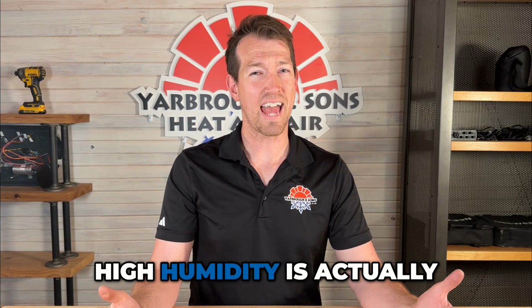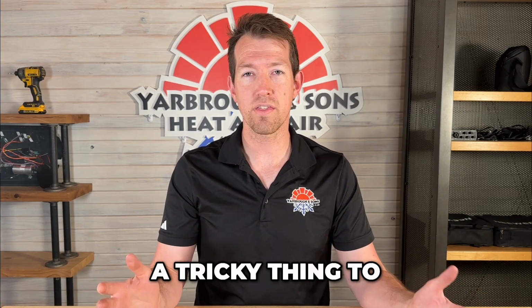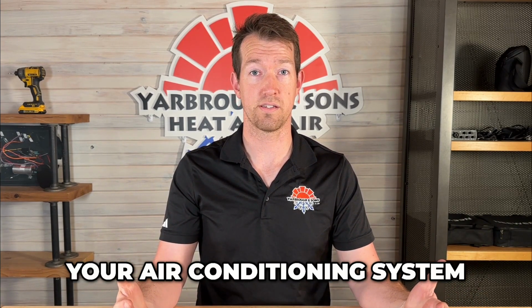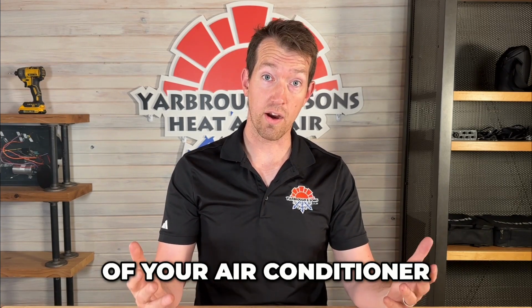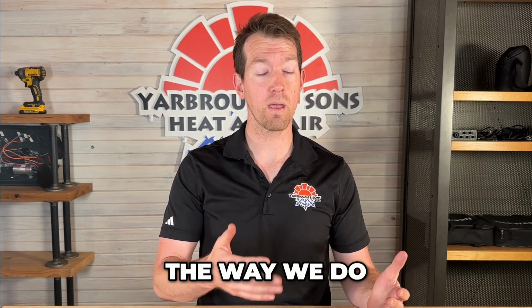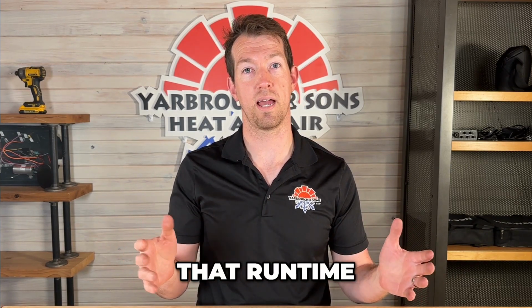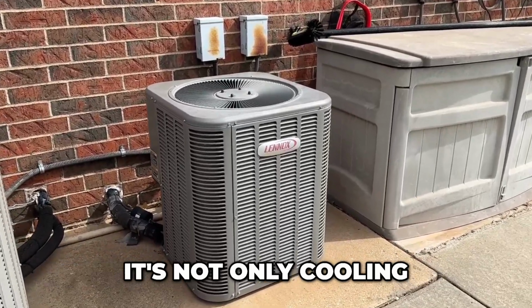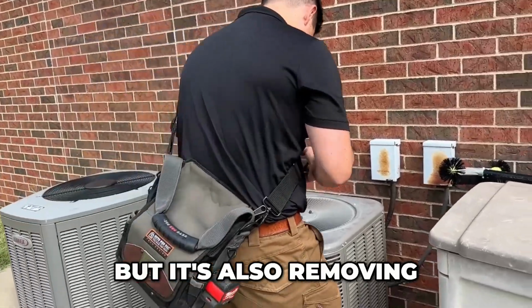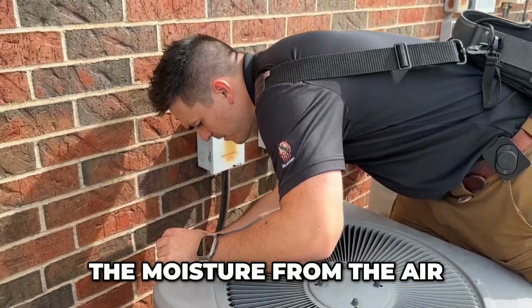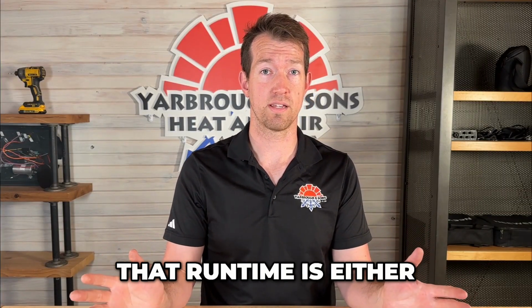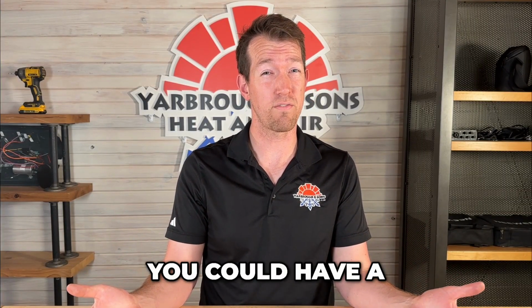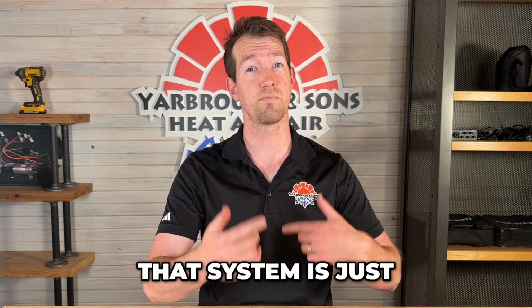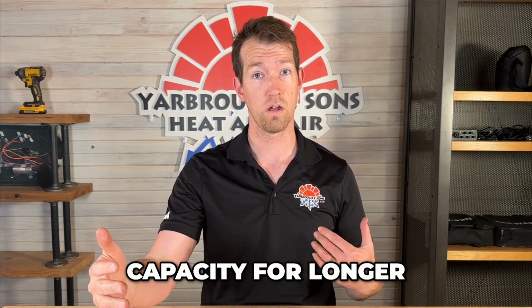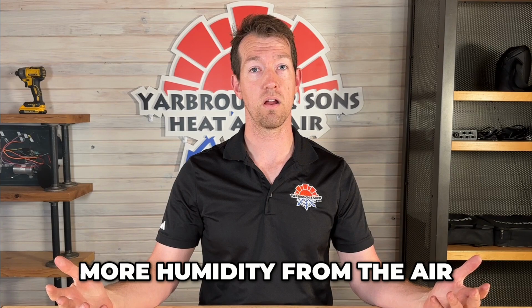Thirdly, high humidity is actually kind of a tricky thing to address with your air conditioning system. Part of the job of your air conditioner is to remove humidity. The way we do that is we increase that runtime. So as your air conditioner runs, it's not only cooling your house off, but it's also removing the moisture from the air. The way we increase that runtime is either A, you could have a variable capacity system where that system is just running at a lower capacity for longer. So it's going to remove more humidity from the air.